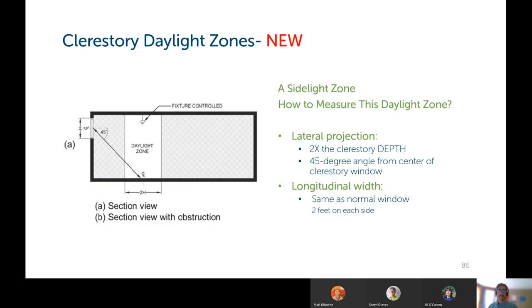A new addition or call out to this code are clerestory window daylight zones. So windows that are up really high on a building. This is showing how to calculate the daylight zone for a clerestory window. The lateral projection of the daylight zone is twice the depth of the clerestory window. That's actually how big that window is itself, not the floor to the bottom of it, just how tall that window is. So twice that amount projected at a 45 degree angle from the center of the window to the floor. And then you project that up to see any light fixture that is within that daylight zone would need to be controlled. And longitudinally, you would just go 2 feet on either side of that clerestory window projected down on the ground.